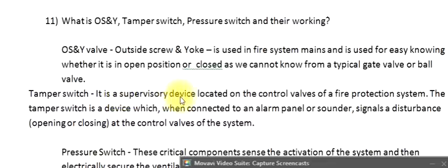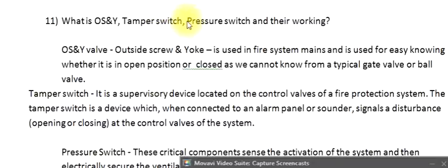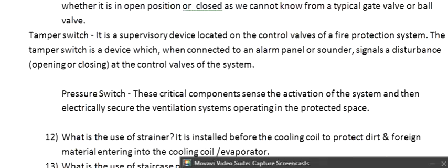Tamper switch: it is a supervisory device located on the control valves of a fire protection system. The tamper switch is a device which, when connected to an alarm panel or sounder, signals a disturbance — opening or closing — at the control valves of the system. Pressure switch: these critical components sense the activation of the system and then electrically secure the ventilation systems operating in the protected space.